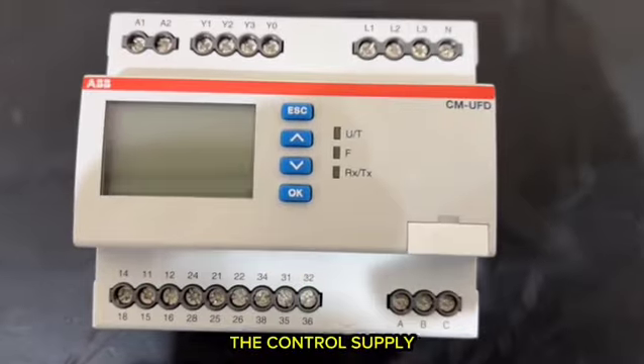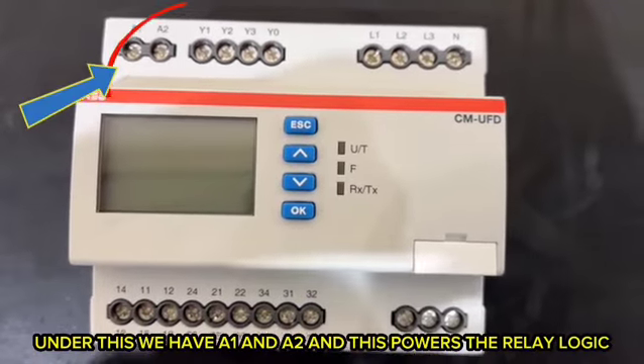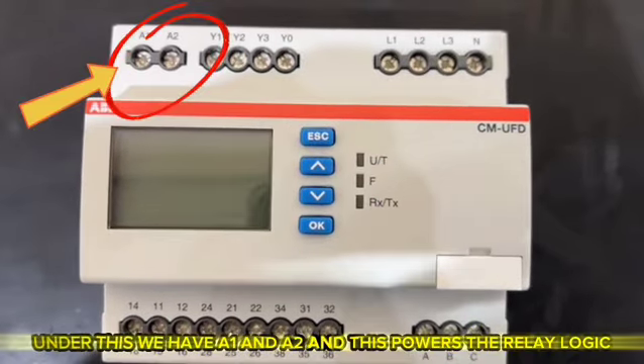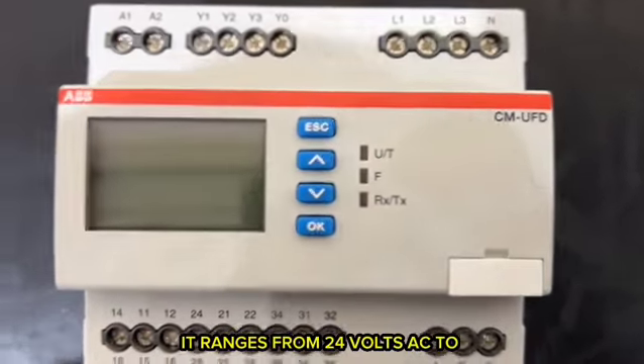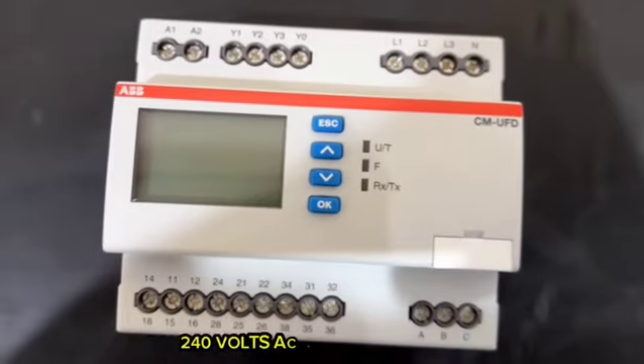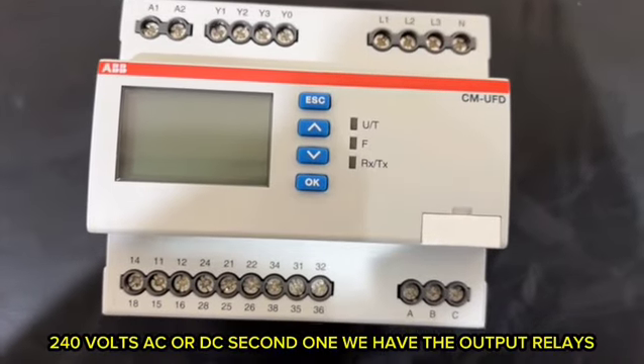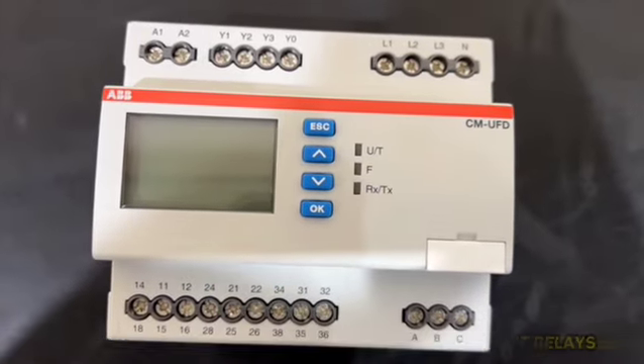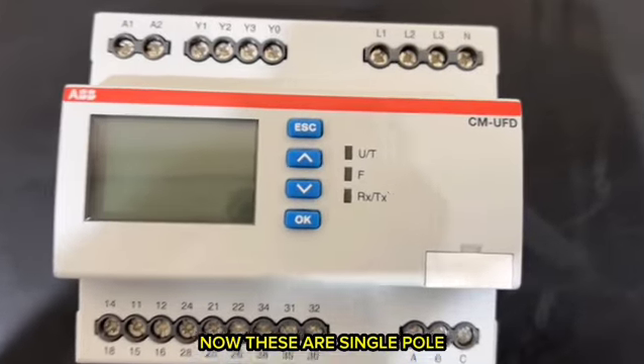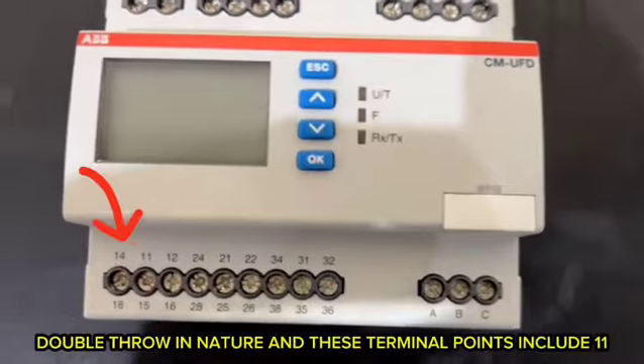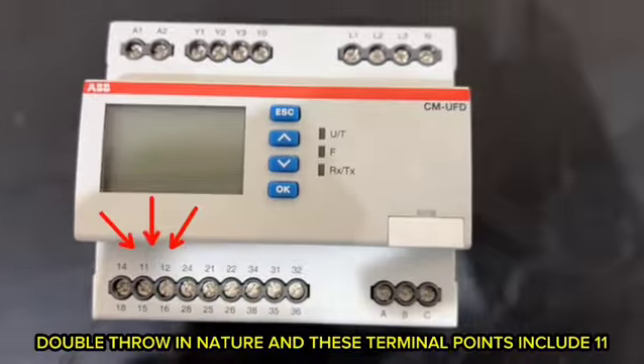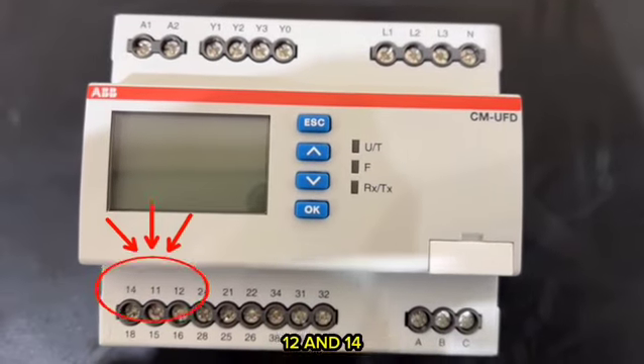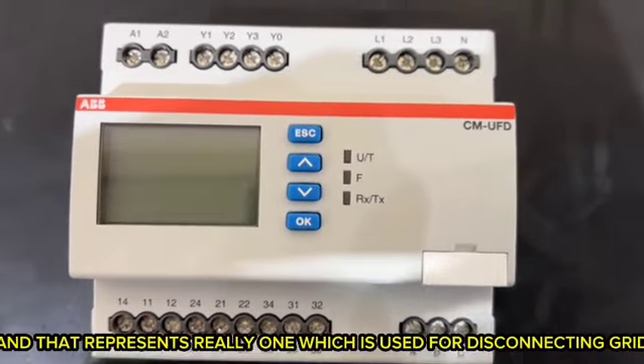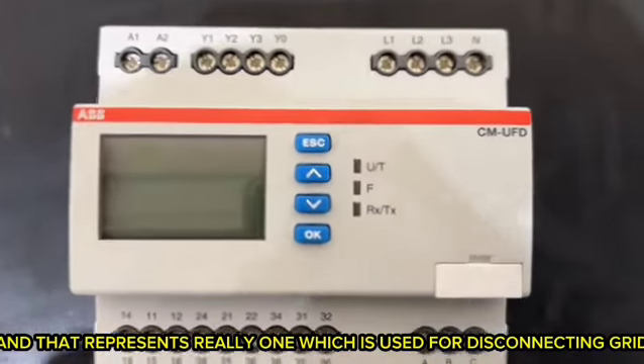So the control supply. Under this we have A1 and A2, and this powers the relay logic. It ranges from 24 volts AC to 240 volts AC or DC. Second one, we have the output relays. Now these are single pole double throw in nature, and these terminal points include 11, 12 and 14, and that represents relay 1, which is used for disconnecting the grid.